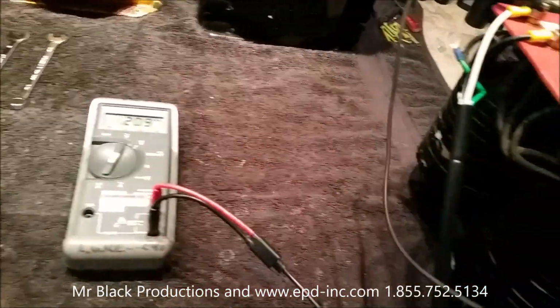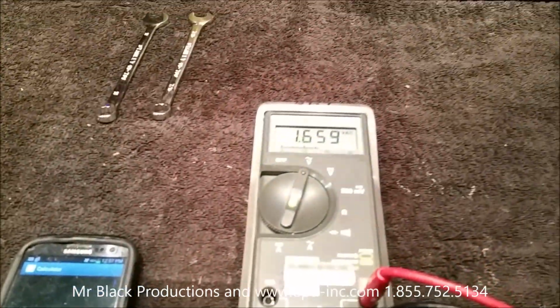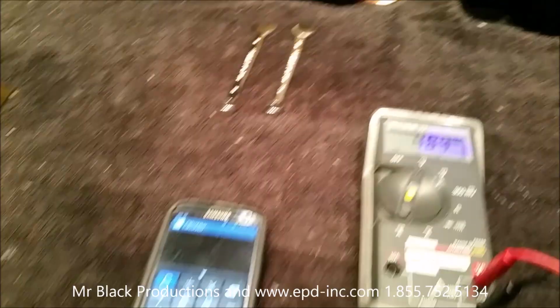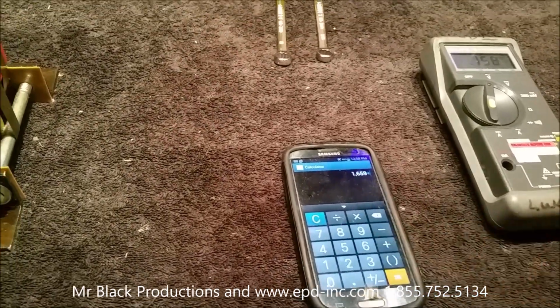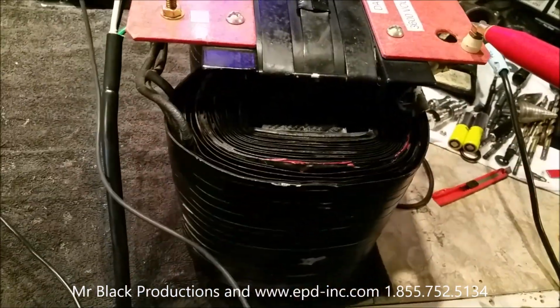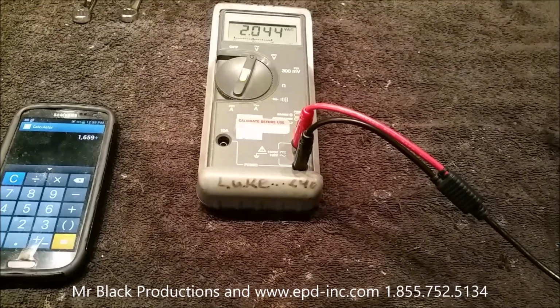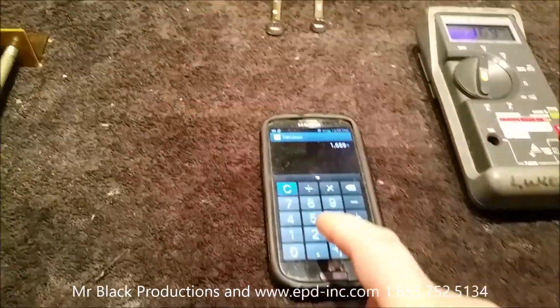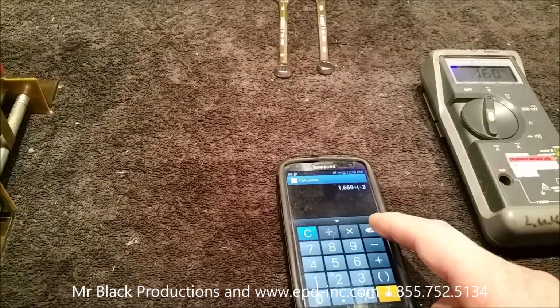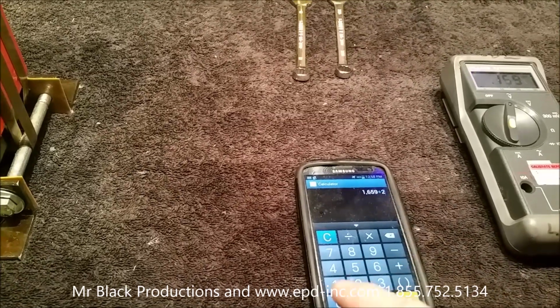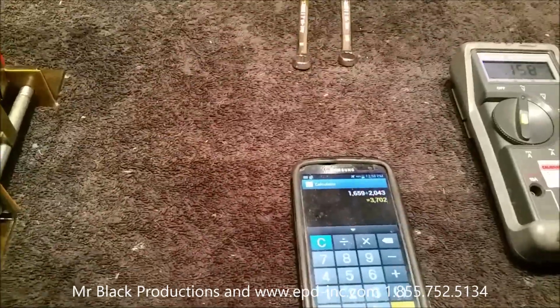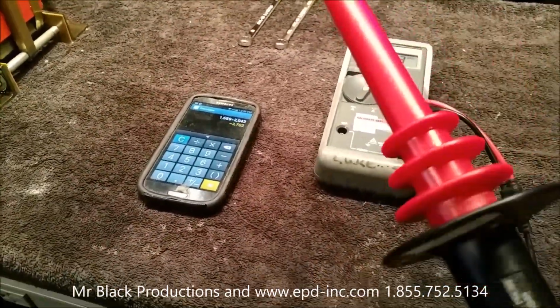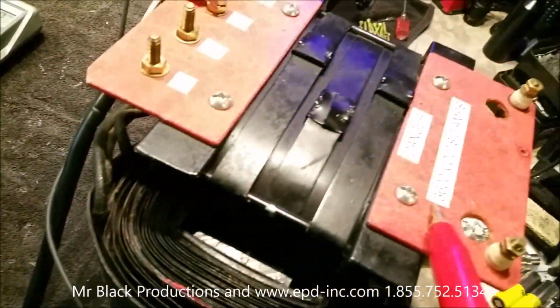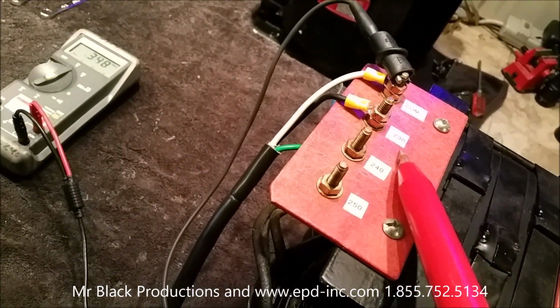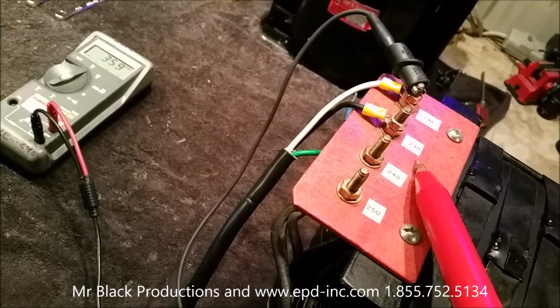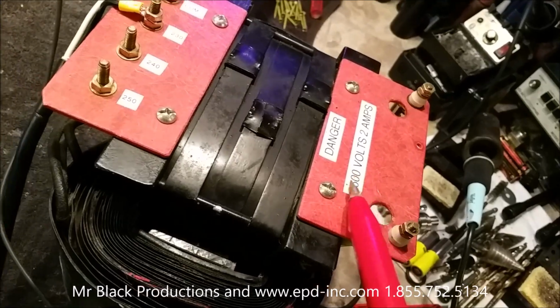We'll take our test lead to the secondary, and that's showing us 1,659. So we take 1,659 plus our second secondary tap, 2,043, plus 2,043 equals 3,702 volts. Remember, this is giving me about 80 volts of plus current. Let's see what this is labeled at: 3,600 volts, on the high common or primary, 230. So we're pretty close. We'll see if this is 2-amp regulated or not.